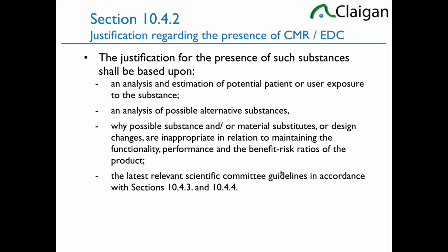But if you have a CMR or EDC above 0.1% by weight in a material that's invasive or contacting the air or gas going in, you need to justify. And there'll be continuous churn throughout the whole thing where people are asking, are you sure? Are you really sure? So on and so forth. Well, so-and-so said this, and then you're going to probably get clippings or mails from other people. The sky is falling, so on and so forth. In practice, probably the most time-consuming part for the people involved in this is not the justification per se. It's the churn and concern you're going to get from management, that they're worried, what if it doesn't pass? And then can you present to so-and-so about why you think the justification is going to work? Or this competitor has a replacement. Will that cause problems for us? Especially if the competitor has a replacement at the 11th hour before you submit your justification. It is a lot of churn here.